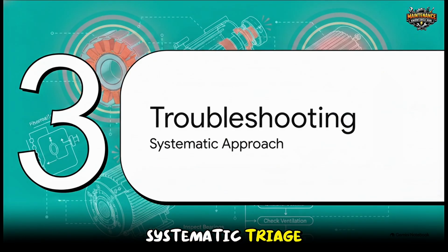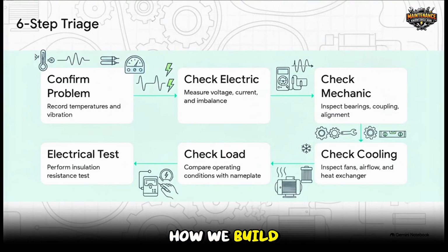We need a systematic triage. Let's walk through how we build this investigation methodically. First, we confirm the baseline data, actually recording the temperatures, current, and vibration levels. Then, we sequentially clear the systems.